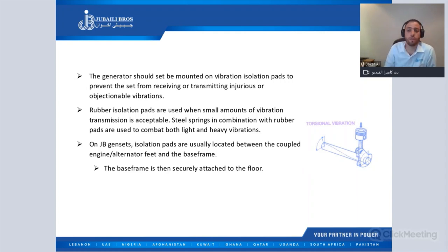Now we'll talk about the generator mounting and the anti-vibration. The generator should be mounted on vibration isolation pads to prevent the set from receiving or transmitting injurious or objectionable vibration. So we have to install rubber mounting under the generator set before putting this generator set inside the room.